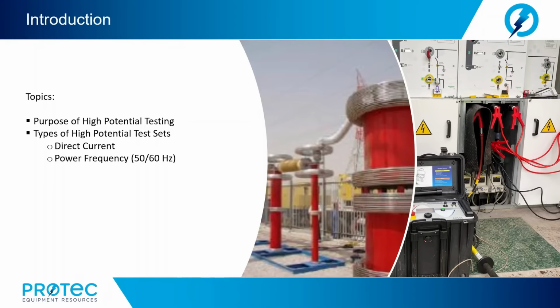All right, in electrical testing, a high potential test or pressure test, dielectric withstand, or high-pot test is an electrical test performed on a component or product to determine the effectiveness of its insulation. The test may be between mutually insulated sections of a part or energized parts and ground. The test is a means to qualify a device's ability to operate safely during rated electrical conditions. If the current through a device under test is less than a specified limit at the required test potential and time duration, the device meets the dielectric withstand requirements.